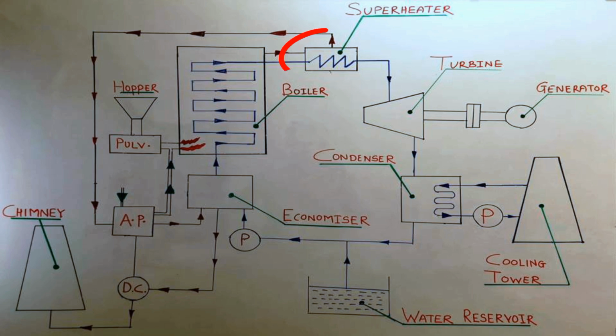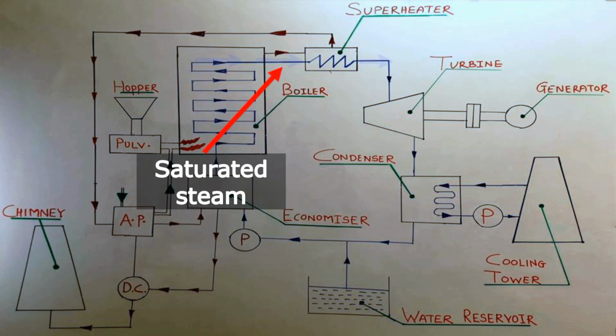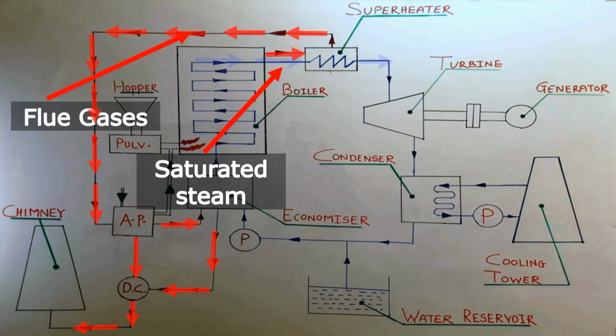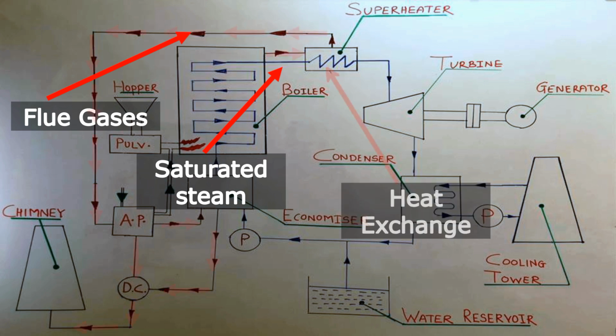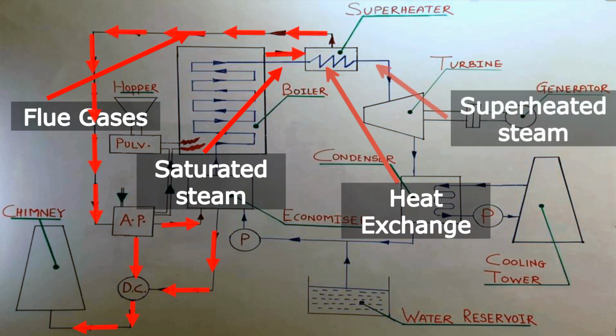Now the next element is a superheater. One can see here the steam is coming from the boiler and allowed to pass through the superheater. At the same time, through this animation, you can see here the superheater is placed in the path of the flue gases. So superheater takes the heat from the flue gases and supplies it to the steam in order to convert saturated or wet steam into the superheated steam.